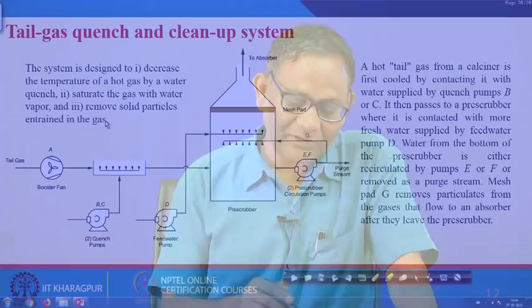So, now you can develop a fault tree for this. What is the system failure? If any one of the objectives is not fulfilled, that is failure. If the booster fan does not work, that also leads to failure, because tail gas will not come here. If either of the quenching pumps does not work, then temperature will not be cooled. If the feed water pump does not work, water saturation will not take place.